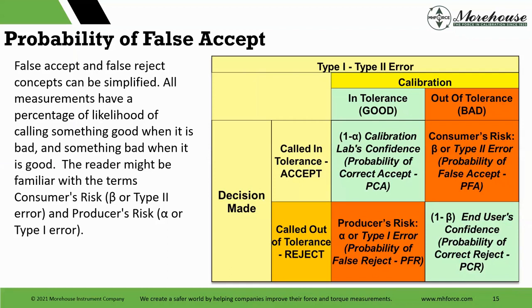There's always some probability that a measured value falls within an acceptable region when the actual value lies outside that region. This results in our false accept condition. There's also some probability that a measured value falls outside an acceptable region when the actual value lies inside that region, and that's our false reject condition. National standard recommends compliance testing should control false accept risk to be no more than 2%. False accept and false reject risk are only one part of a full risk acceptance.